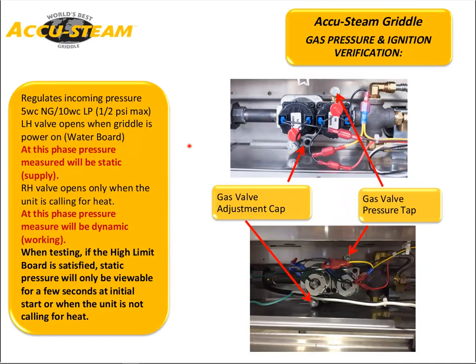If we move on, this is the gas valve for our AccuSteam Griddle. You'll notice that the coils are very similar. It's a very similar design, just the tap is relocated for easier adjustment due to the reorientation of the valve, and the adjustment is in the same place underneath the pilot valve. Our griddles work in a similar way. You won't be able to see the static pressure for very long on these. When you first power the griddle on, the pilot valve is opened almost straight away, so long as there is no high limit or issues like that. You will see static pressure for around about 5 seconds. The ignition system will kick in, the main valve will open, and at that point you'll see your dynamic pressure. Again, dynamic pressure should be set to 5 inches water column, and that's across the board, any size griddle, 24, 36, 48, doesn't matter how many burners it has, 5 inches is the set standard for these griddles.